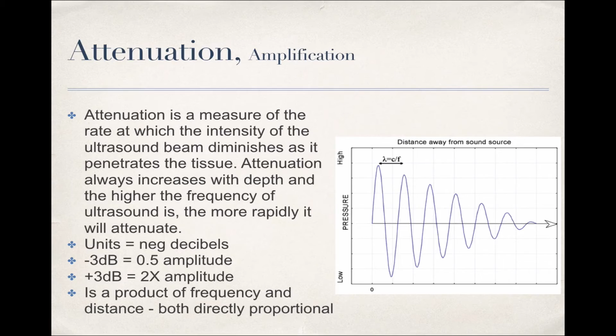The other thing to note about the amplitude and the attenuation is that it's directly proportional to the frequency and the distance, and that's why those high frequency probes that we use for like vascular studies or to put in lines for procedures, that's why they're only used for superficial tissue, because those are high frequency, higher amplitude waves. But the attenuation is directly proportional to the frequency and the distance. So the more distance you have and the higher frequency of the ultrasound wave that you use, the higher the attenuation will be. And that's why those high frequency transducers do not penetrate into tissue very well.